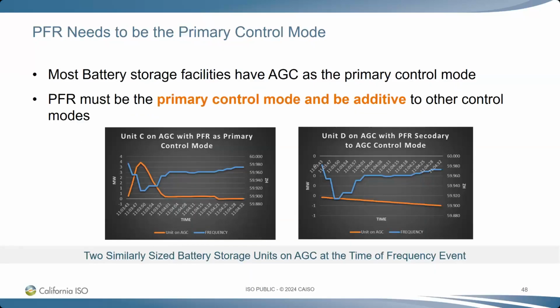But what he really wanted to make the point on is that for frequency, you want to make sure that you're on a primary control mode. He went through an example where most battery storage facilities have AGC as a primary control mode, and if that's the case, it must be on the primary control mode and be additive to other control modes. Here's an example.